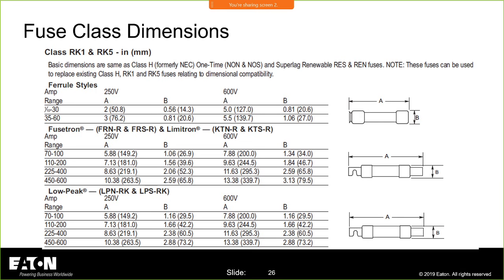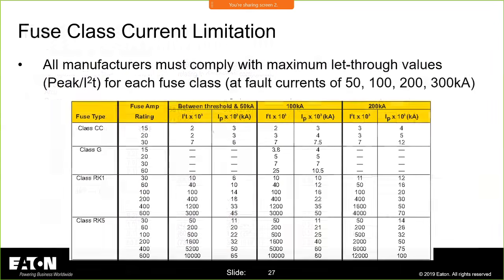And you'll notice the RK1s have those rejection features, right? And on these, it's only on one side of the fuse. So every fuse is going to have rejection so that you don't put the wrong fuse in the wrong holder and put a less capable device into the wrong slot. And then you have your fuse class current limitation. So in the standards, all of the manufacturers have to meet the requirements, and they have a maximum let-through value that they're allowed for each of these fuse classes.